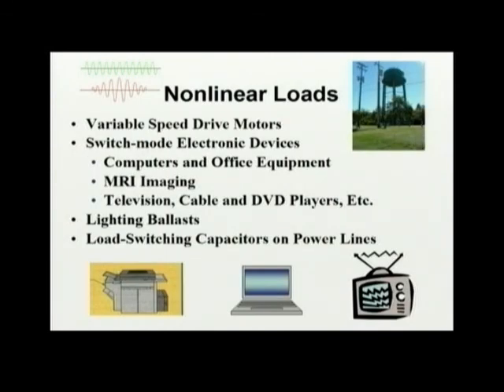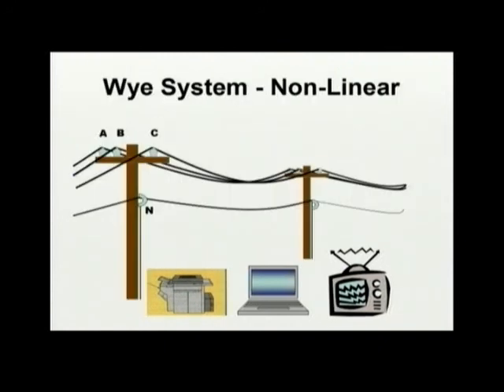Since the early 1970s, we have seen a dramatic increase in the use of modern electronics, which are nonlinear loads. Nonlinear loads change alternating current to direct current. Direct current is current which travels in only one direction, as from a battery. Electronic devices change the frequency of AC current to speed up or slow down a process or signal. Variable speed drives, switch mode electronic devices such as copy machines, MRI or magnetic resonance imaging, TV, cell phones, digital clocks, radios, some types of halogen and fluorescent lighting ballasts, load switching capacitors on power lines, and hundreds of other electronic controls use nonlinear loads and contribute to electrical pollution.